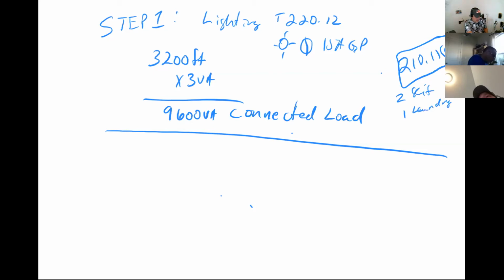And then it also lays out the bathrooms, right? Yeah. Bathroom circuit. Be careful, because I could have 4 bathrooms, but I would still only have to have 1 20 amp circuit, because I can share all the power. Now it's not lighting, it's just the receptacle loads, right? So it's just for receptacles. And then in the new code book, the 2017, they added 1 more for the garage. Thank God, finally something that makes sense. I need 3 circuits in my garage, really what I need. I've added 3 circuits to my garage. Exactly. All right, so 2, 3, 4, 5 minimum required 20 amp circuits.